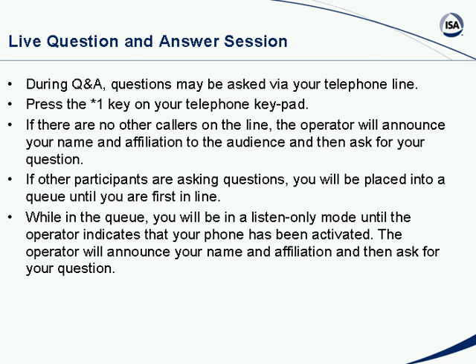A question from Joseph Martinez of Cedigree Technology: back on the topic of synchronization, will the ISA 100 standard recommend or suggest more expensive, more elaborate real-time clock circuitry to deal with the problem of time drift? The current thinking is that it will not — we can accommodate the level of time synchronism required with state-of-the-art circuits currently shipped with the 802.15.4 radios. Keeping the cost of the end nodes down, the way that's going to be done is by keeping relative time in the end nodes and keeping absolute time at the higher levels in the architecture.